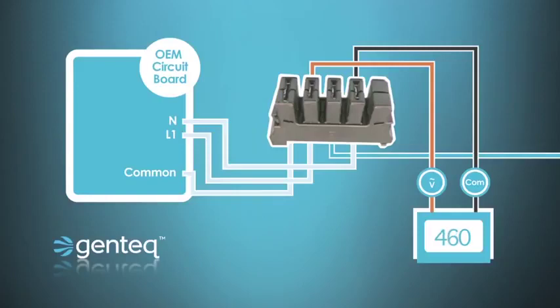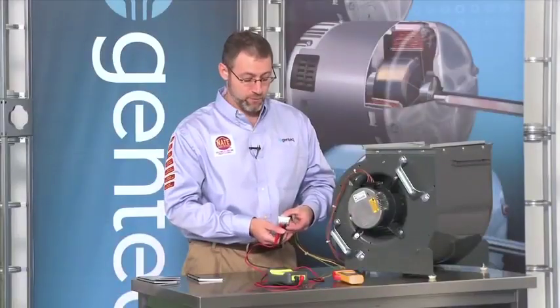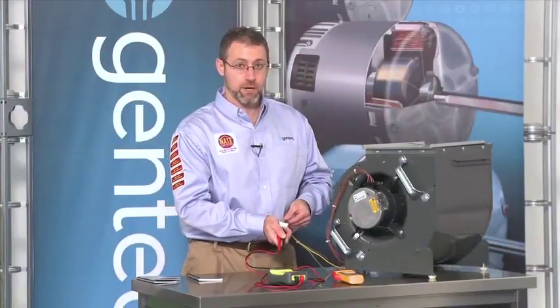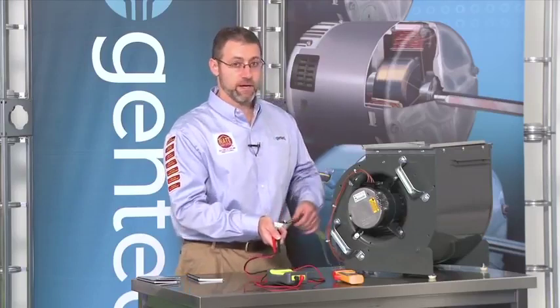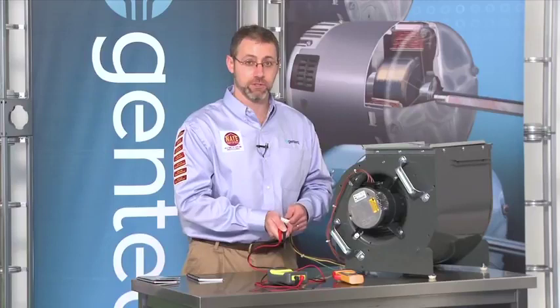We're still going to have our meter leads on the black L1, and in most cases the white, where on this manufacturer they used yellow for the N or neutral position. So regardless of the voltage, our meter leads are going to stay in the same place. If we have the voltage on our plug that we should have from our system, then we can move on. If we do not have that voltage, we need to find out where that was lost, fix that problem before we can move on so that the motor has proper high voltage.